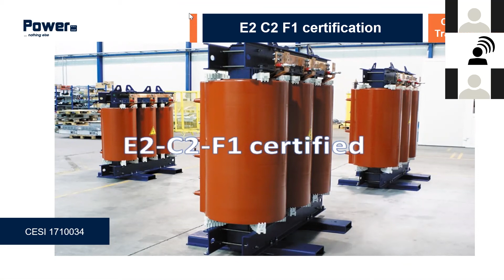Another very important point we noticed, especially in the Baltic area, but also in some countries like Ukraine, is that somebody is playing with the eco-design rules. On the left side, you can see a typical specification for a tier 1 transformer with the losses for, this is 100 kVA, I just took a small transformer as an example. Just ensure that in the tolerance on losses, you have 0%. It must be written, and also the level of losses must be specified: eco-design, tier 1 or tier 2.